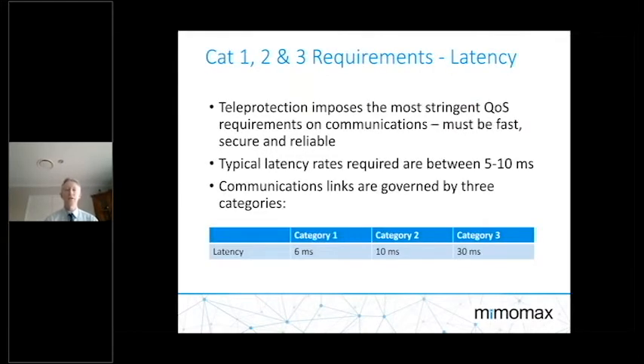In terms of latency requirements, teleprotection really imposes the most stringent QoS on a communication system. It must be fast, secure, and reliable, and latency rates must fall between 5 to 10 milliseconds. That relates to the energy equation and reducing the amount of energy in a fault cycle, and also reacting ideally within one cycle.